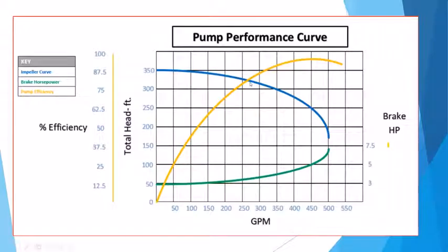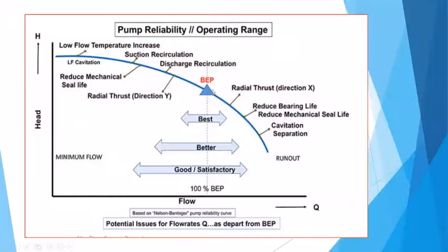Again, getting back to that proper pump curve, especially today with less and less water available in our irrigation systems, where the water level is affects this efficiency and the amount of head that you've got to lift. Let's say, I know some friends of mine over in the Madeira area, their water level drops as much as 40 and 50 feet between the beginning of an irrigation season and the middle or end, or even on weekends when everybody else is pumping. Well, that's all in how far you've got to lift that water from the ground and bring it up. And so again, that slides where we are at for best efficiency point.